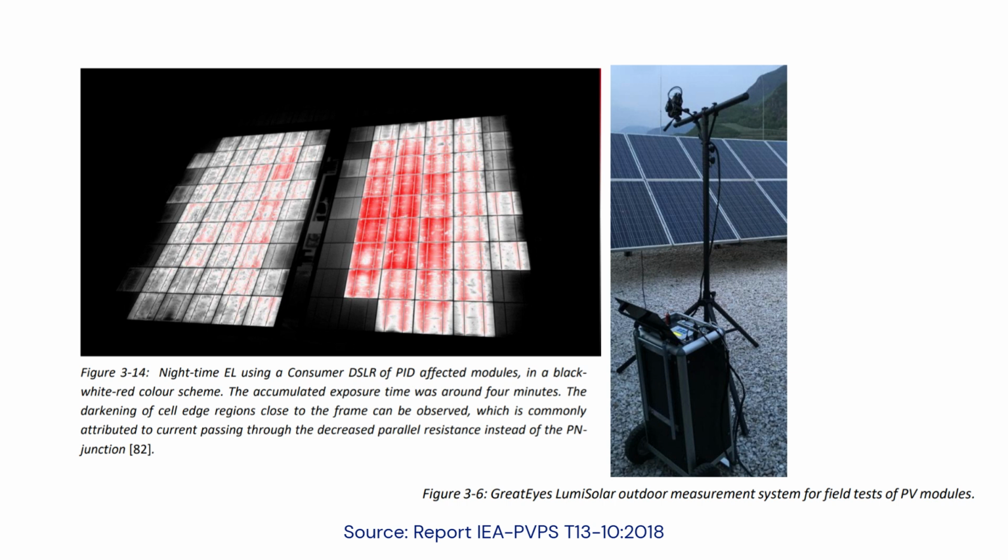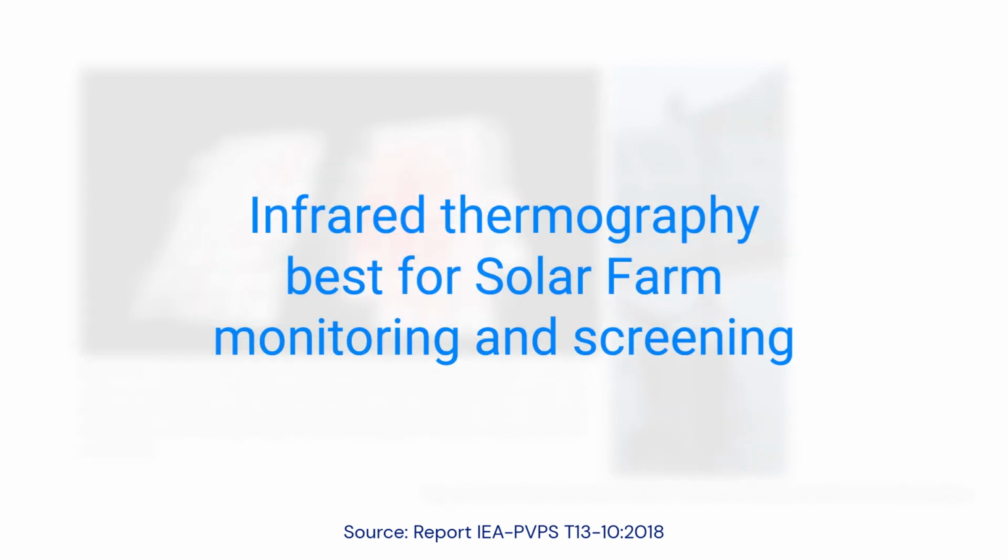The method also demands close-range access, specialized power supplies, sensitive cameras, and trained personnel, making it labor-intensive and costly when applied across thousands of modules. Furthermore, environmental factors such as ambient light, temperature, and wind can affect image quality in outdoor conditions. As a result, EL imaging does not scale well for routine inspections and is instead recommended for targeted failure analysis on selected modules, rather than comprehensive field-wide monitoring.